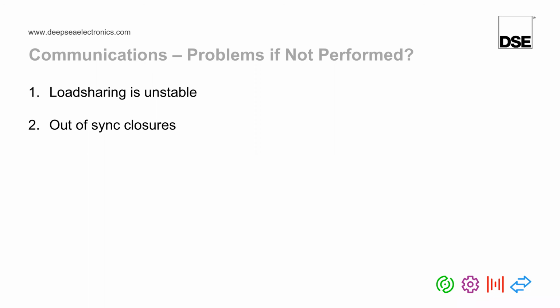But this is not necessarily a problem with the 8610 Mark II controllers. The advantage with using the 86 Mark II controllers is that you can actually wire two MSC links. That means if the first MSC link fails, the modules automatically revert to the second MSC link, effectively giving you MSC redundancy.